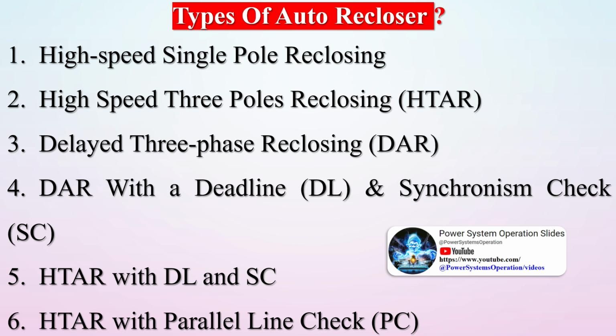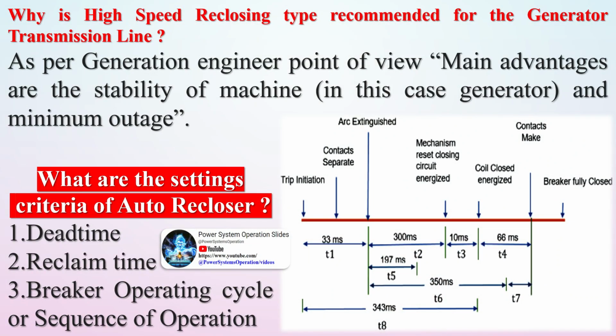And, of course, continually de-energizing and re-energizing a line would create a safety hazard as well as potentially degrading network stability and risking further damage to assets. For these reasons, auto-reclose controllers are designed to lock out after a certain number of trip-reclose cycles, usually 2, 3, or 4 cycles, depending on the application.